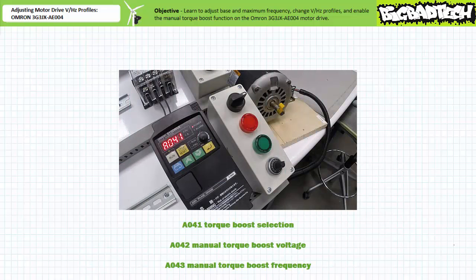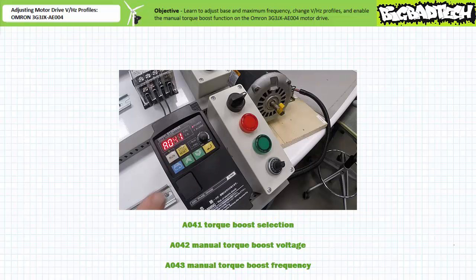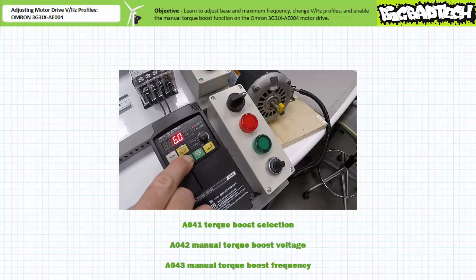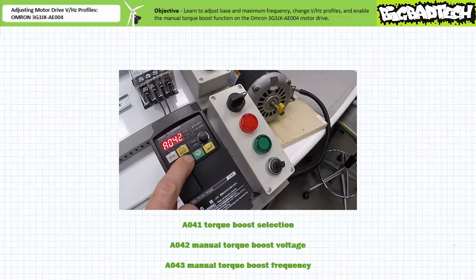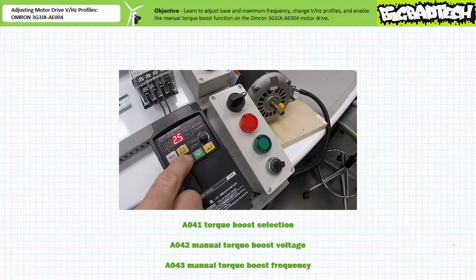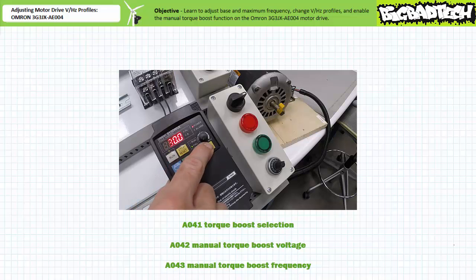Leave extended function parameter A041, torque boost, in the default 00 manual state. Navigate to extended function parameter A042, manual torque boost voltage. Select mode, increment to plus 20 percent, then select enter to save it. Navigate to extended function parameter A043, manual torque boost frequency. Select mode, increment it to 30 percent of base, or 18 hertz, and select enter to save it.